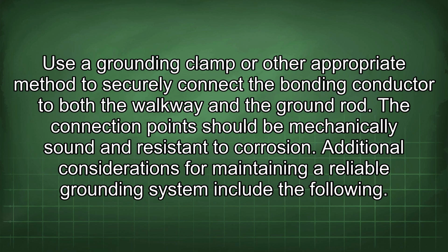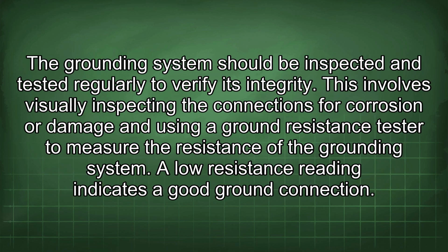Additional considerations for maintaining a reliable grounding system include the following. The grounding system should be inspected and tested regularly to verify its integrity. This involves visually inspecting the connections for corrosion or damage and using a ground resistance tester to measure the resistance of the grounding system. A low resistance reading indicates a good ground connection.